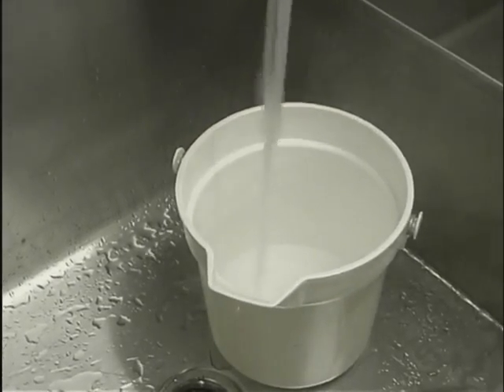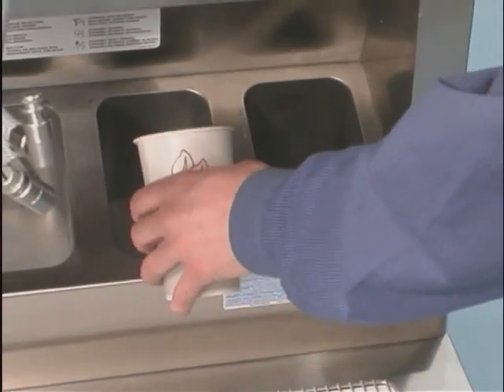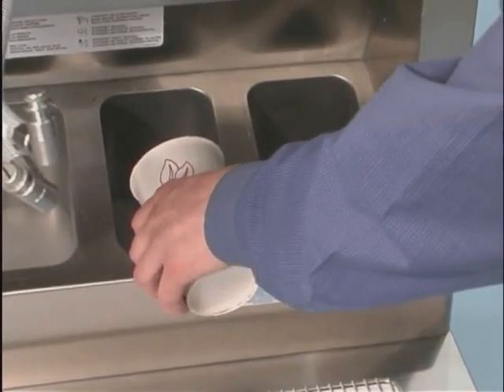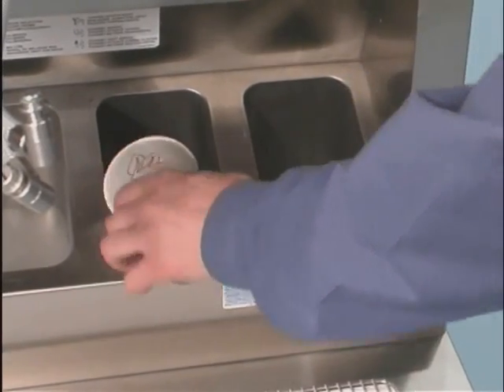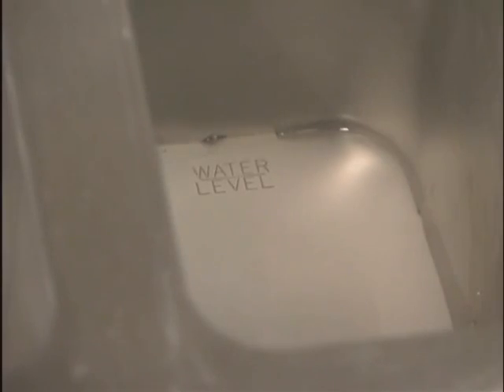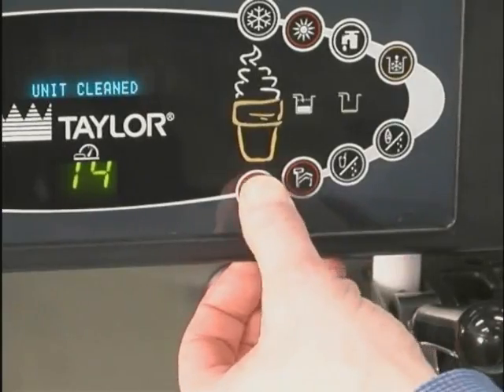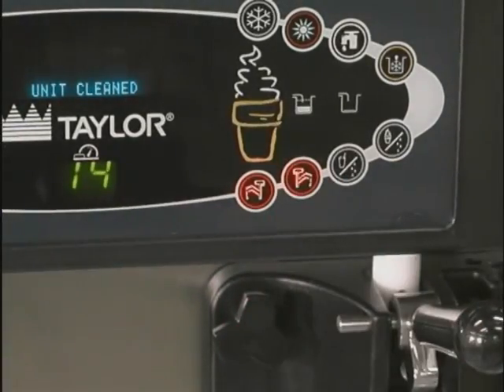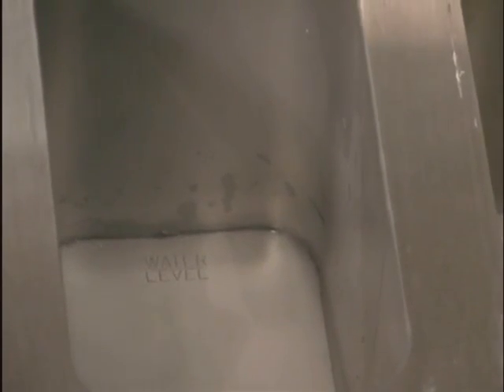With the drain plugs closed, check the water level in the 2 heated topping wells. Fill the wells with water to the indicating mark on the bottom of the well. Place the topping heaters in the on position by touching the topping heater symbols. Caution: as soon as the heaters are turned on, the topping wells will begin heating. This heating process will take approximately 2.5 hours to reach temperature. The water level in the wells should be checked daily.